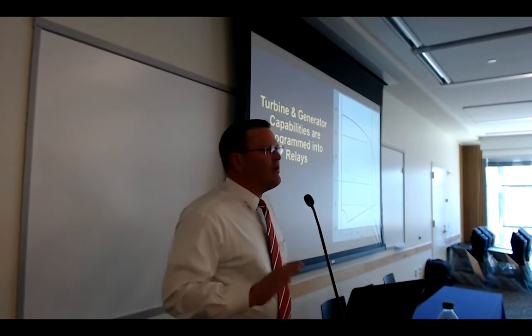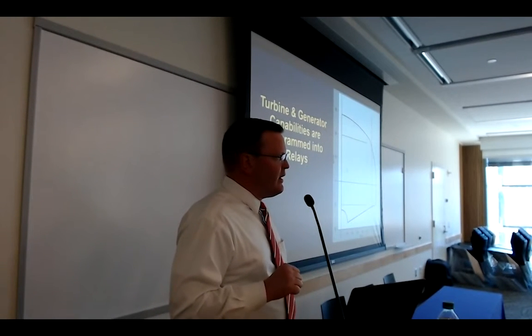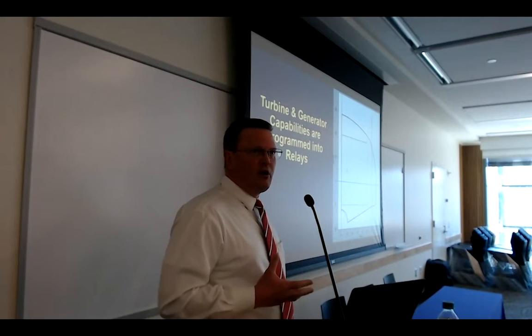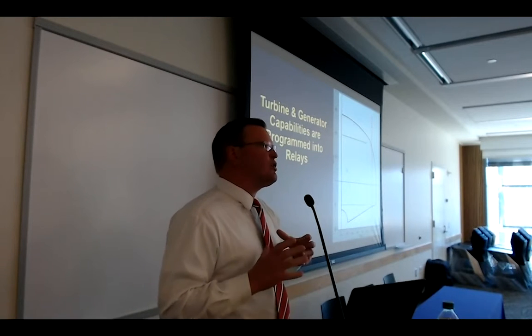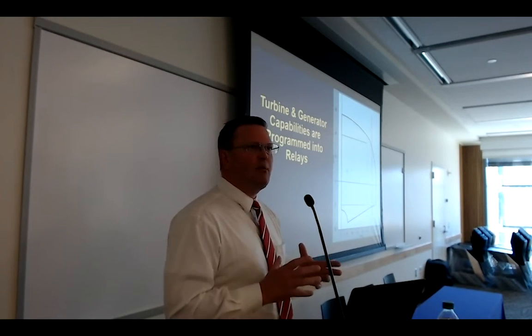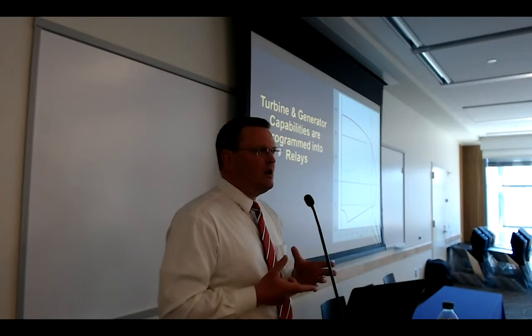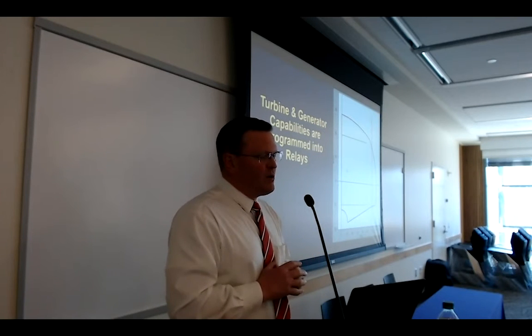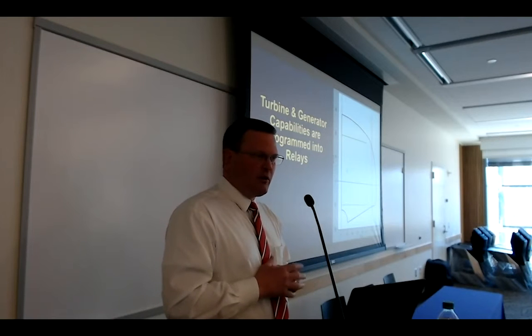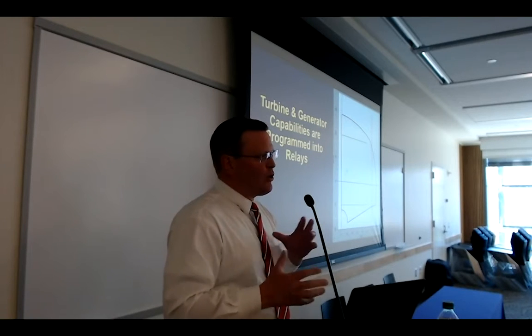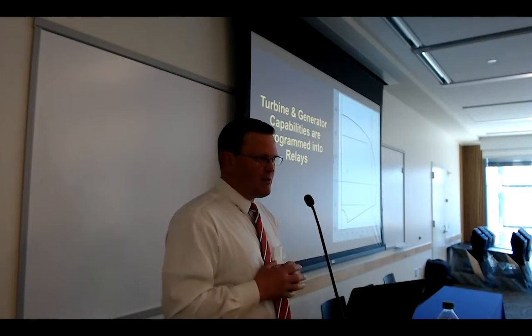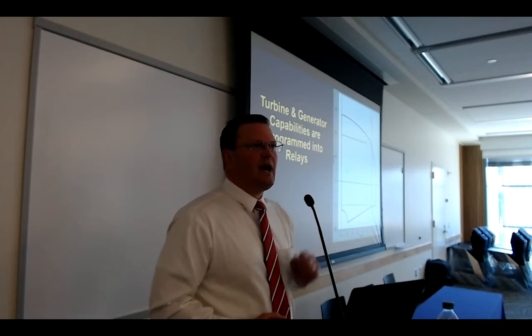The next thing we know about conventional sources is that they have capability curves. Here we see a generator capability curve - that's the round shape - and you've got a vertical line, which is the turbine capability curve. The green box is a controllable area in which the controller happens to be operating, and the little dot is where it's really at.